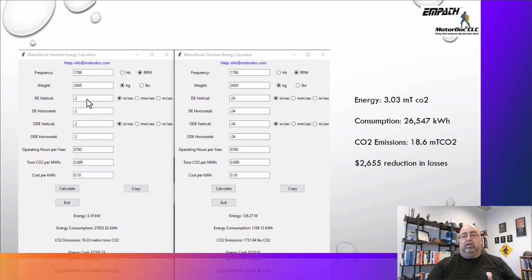This is not overall. So if I have a one-time RPM, 0.2, let's say I have misalignment and I want to tighten that alignment up to get my values down to 0.04 inches per second. So if I put in all the same numbers here, that drops me down from 3.16 watts... 126 kilowatts... to 126 watts. Big difference. There's always going to be some losses. Nothing's perfect, right? Actually, if you get perfect, you have a different problem. You get resonance.